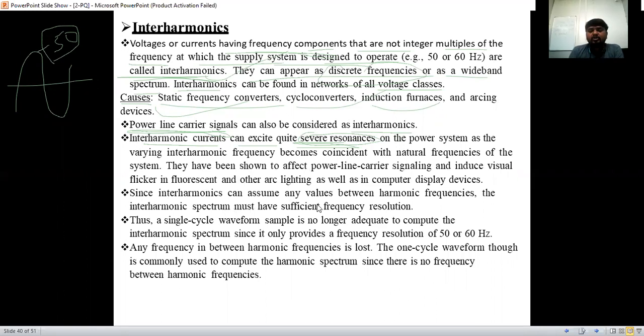Since interharmonics can assume any values between the harmonic frequencies, the interharmonic spectrum must have sufficient frequency resolution. So a single cycle waveform sample is no longer adequate to compute the interharmonics, since it only provides a frequency resolution of 50 or 60 hertz. The 50 hertz is the fundamental frequency. So that is no longer adequate to compute the interharmonics.